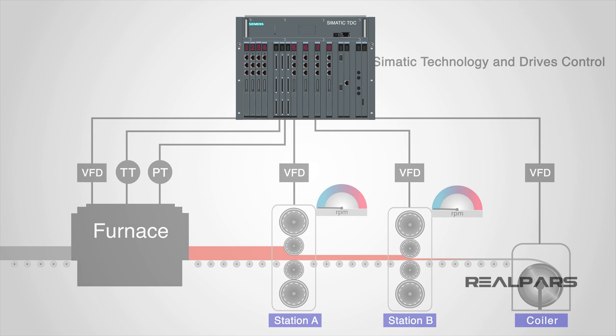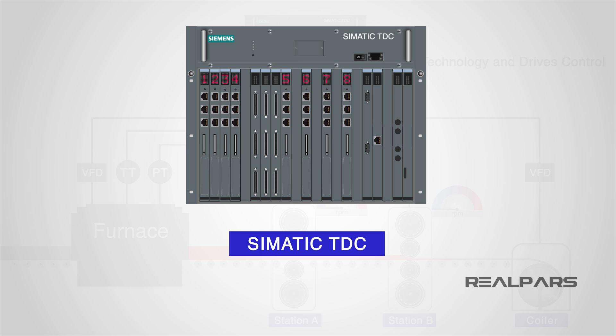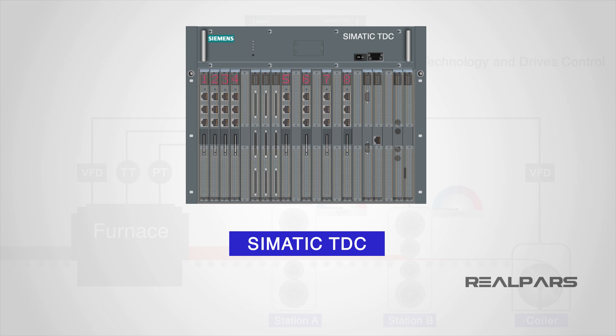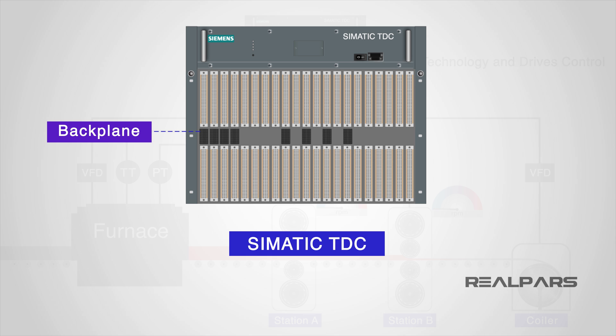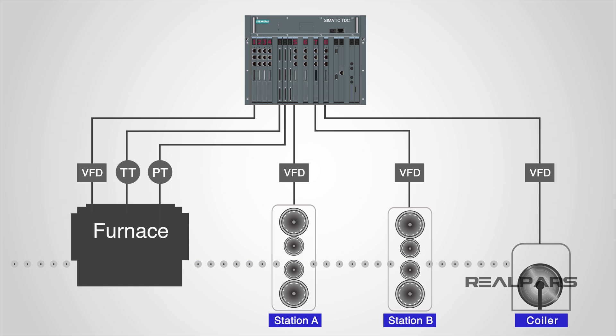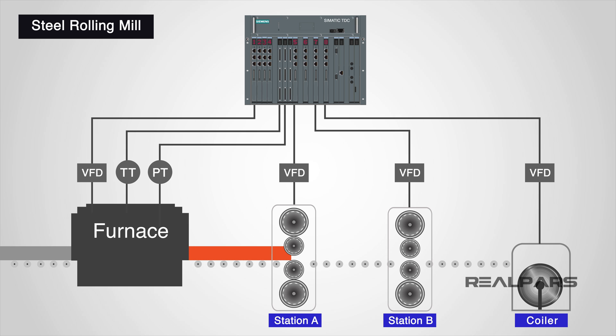So what have we learned today? SIMATIC TDC is a high-performance, high-precision PLC system that allows multiple processors to be mounted in the same rack. This means each PLC controller is connected by the backplane of the rack, so data can be transferred extremely quickly between controllers handling different parts of the plant. SIMATIC TDC systems are powerful motion and closed-loop control systems with a modular design, making them highly scalable to handle small to very large applications. Typically, they are used in large-scale plant environments such as a steel rolling mill, because the complexity of rolling steel means it passes through a number of stations before reaching the end product.